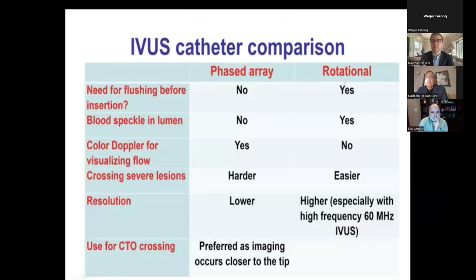So phased array versus rotational, if you were to buy: the rotational catheter has a better resolution, but there is blood speckle in the lumen, and it needs flushing before insertion. It is easier to cross. It's less bulky than the phased array catheter. Resolution is better. But for CTO crossing, because the transducer is closer to the tip, the phased array catheter may be preferred only in that scenario.